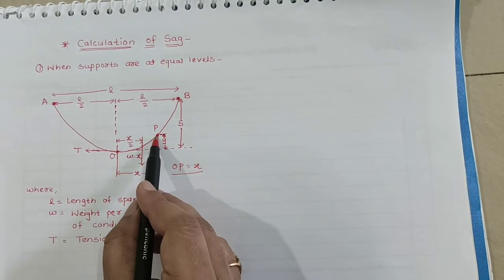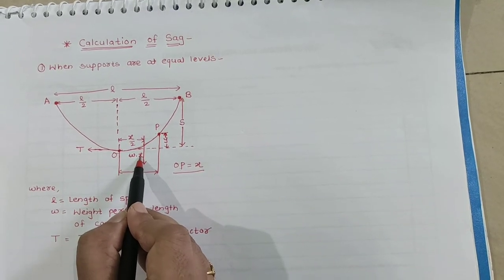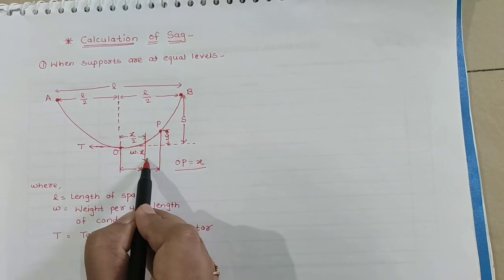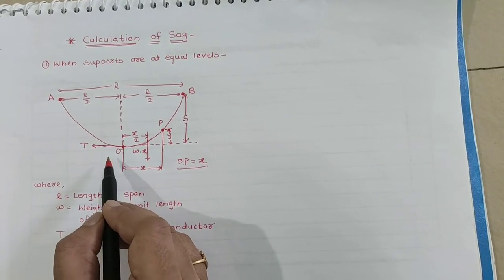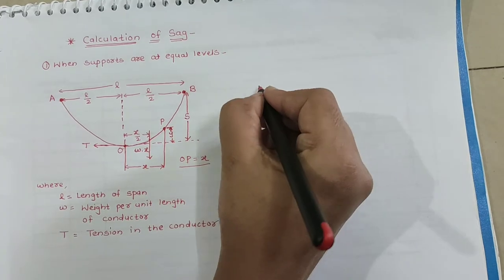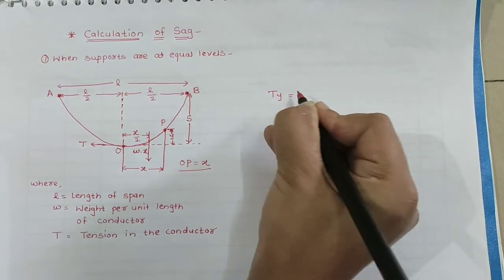So the forces acting on the portion OP are: first one is the weight WX of conductor acting at a distance X/2 from O. Second is the tension T acting at O. Now equating the moments of two forces: TY = WX × X/2.